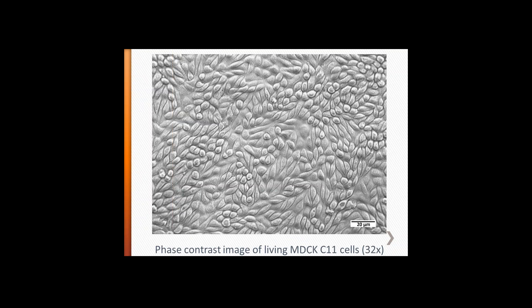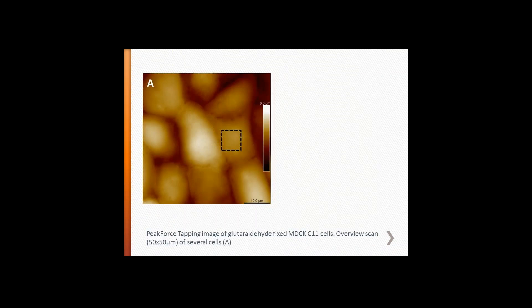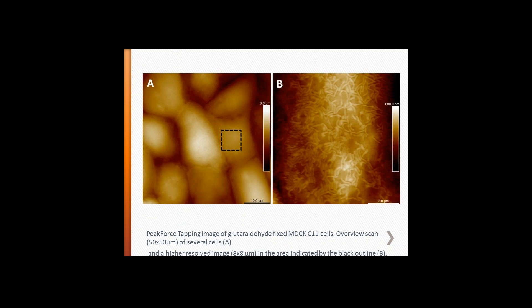These are MDCK-C11 cells as a phase contrast image, and as you can see, the height differences within the cell layer are large — challenging for a common short tip due to shadowing. Using the Peak Force QNM probe, we first imaged glutaraldehyde-fixed MDCK-C11 cells, with no shadowing effect visible. In the indicated square, a higher resolution scan reveals microvilli squeezed down to the surface — nicely shaped but not in their native configuration. Because they are fixed, they are stiff and not flexible, making them easier to image.